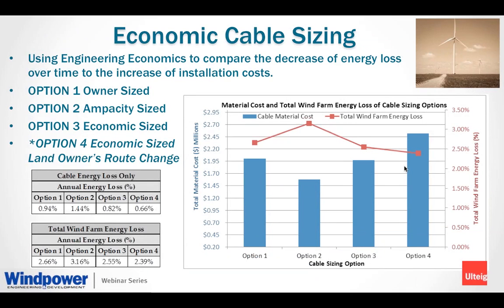So now I'd like to talk a little bit about economic cable sizing. When you upsize conductors, it can be an effective way of reducing energy loss throughout your wind farm. Even small wind farms can have a lot of cable. We had a very small wind farm that had approximately 25 miles of 34.5 underground cable, and the losses were almost half just from the cable. So it's a pretty significant portion of the losses throughout the wind farm project. We like to give our clients an option when we're designing these wind farms.